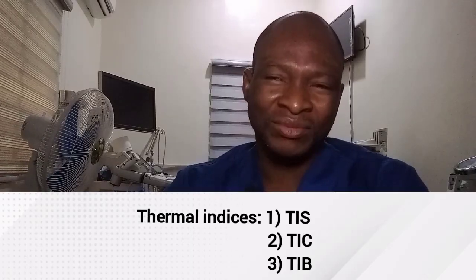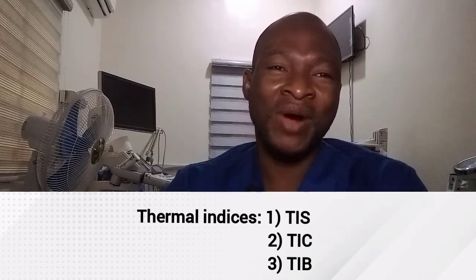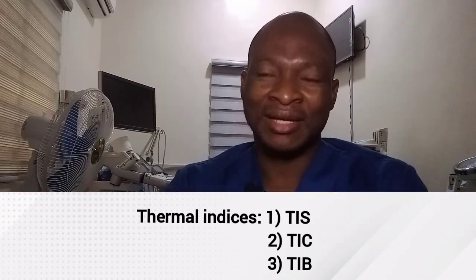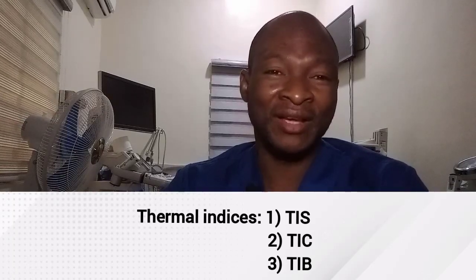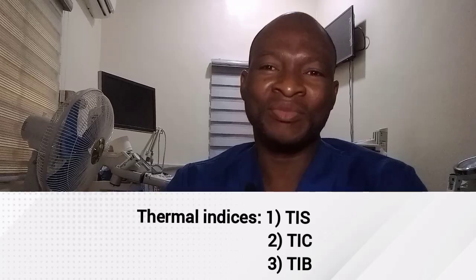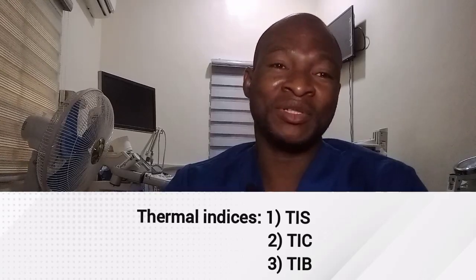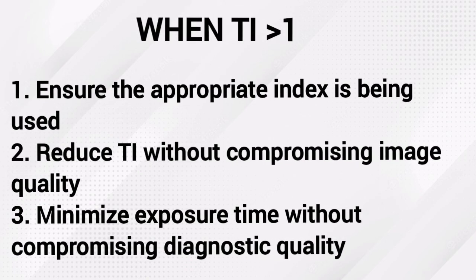It is important to know that a TI value more than one indicates an increased potential for thermal biological effect and should prompt the operator to ensure the ALARA principle is being practiced. So what should you do if the TI exceeds a value of 1? The first thing to do: ensure the appropriate index is being used. So which index do we have? The TIS, the TIC, and TIB. For most applications, it should be the TIS because mostly we deal with soft tissues.